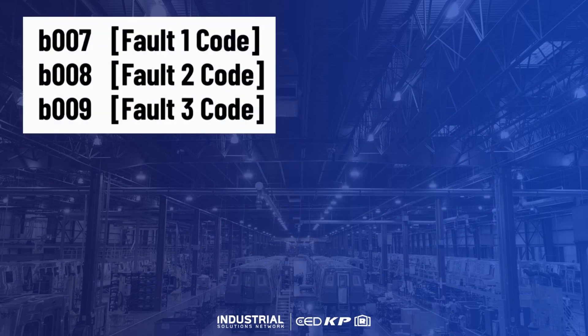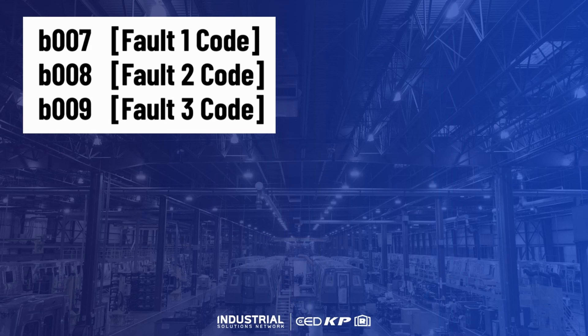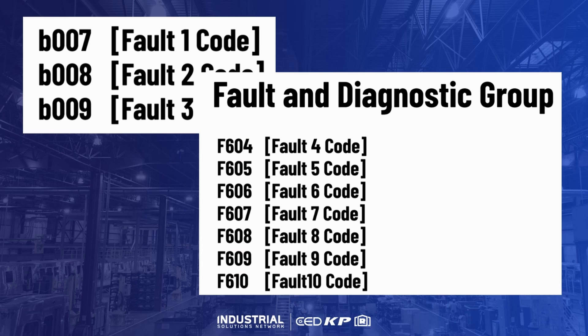Remaining in the basic display folder, parameters B7, B8, and B9 will provide you with the three most recent fault codes. Within the fault and diagnostic folder, you will find the next seven fault codes for the 520 series, for a total of 10 historical fault codes.